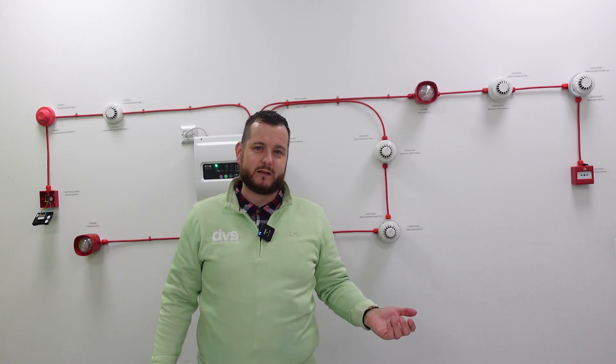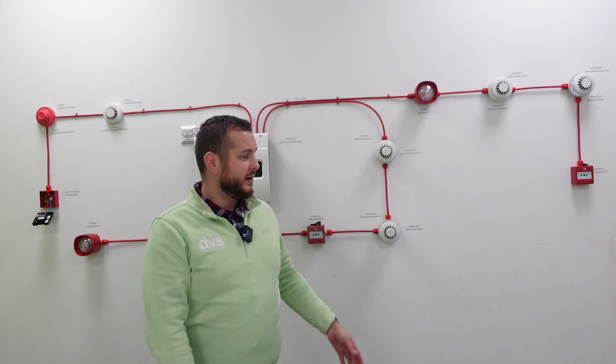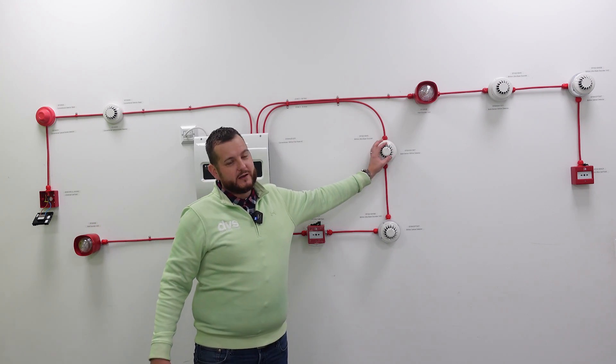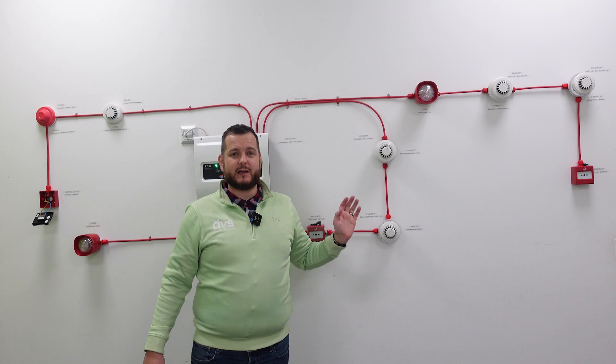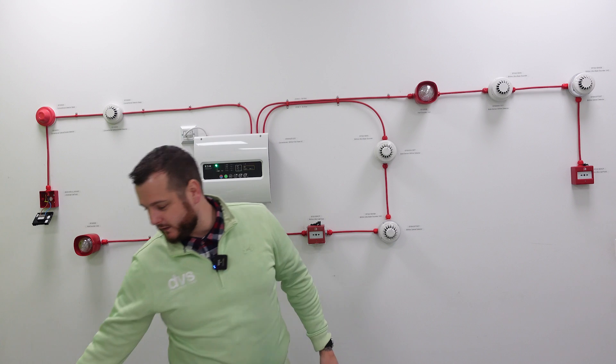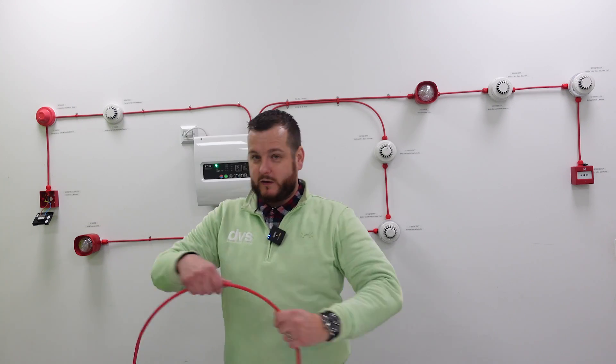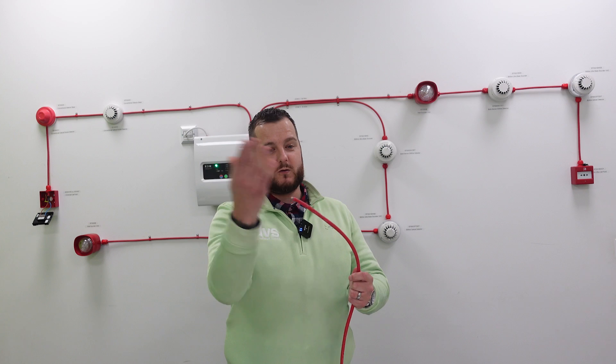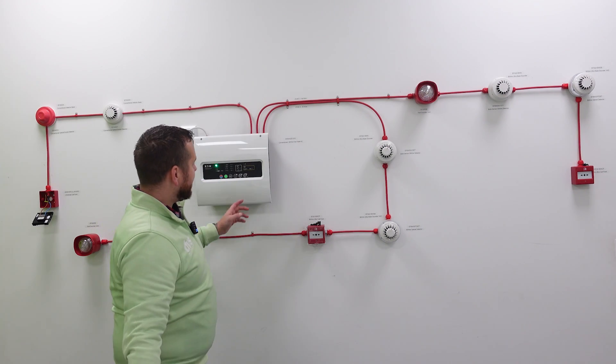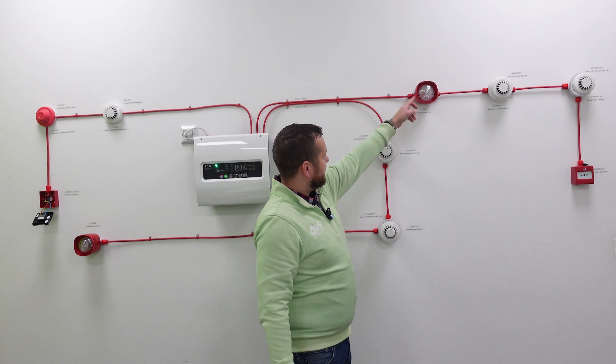The BiWire system by nature allows us to do detection and the alarm circuitry on the same cable, which is quite unique. There are some other manufacturers out there that can do that, but with Eaton product, if you use the BiWire Flex panel and you use the BiWire devices, they do need to be the same. Don't put other people's devices on the same circuit.